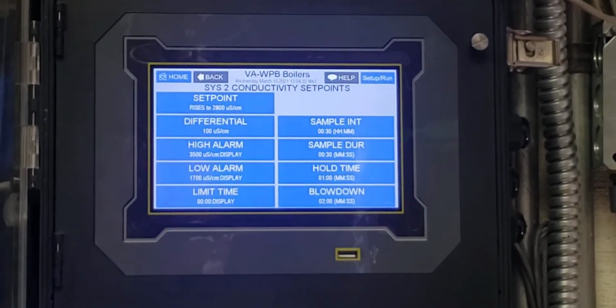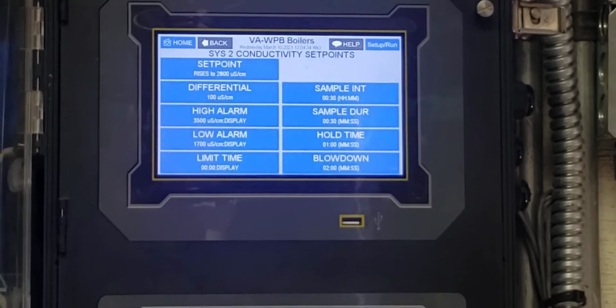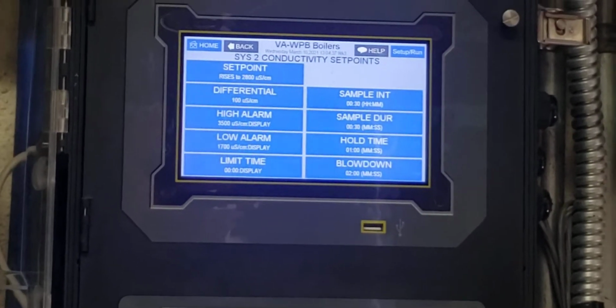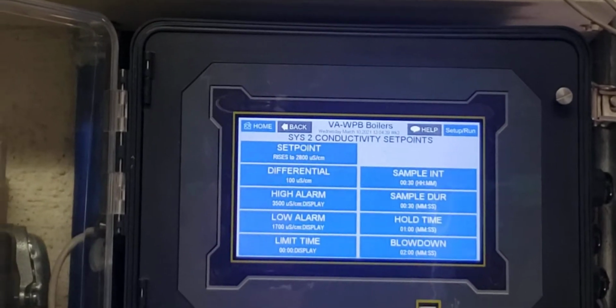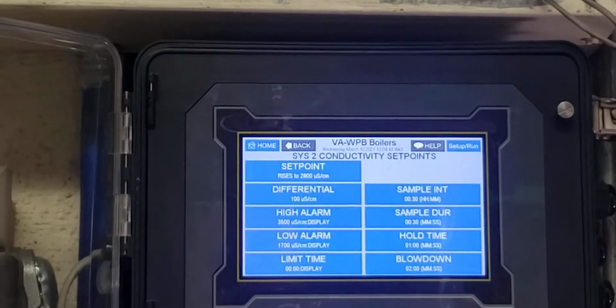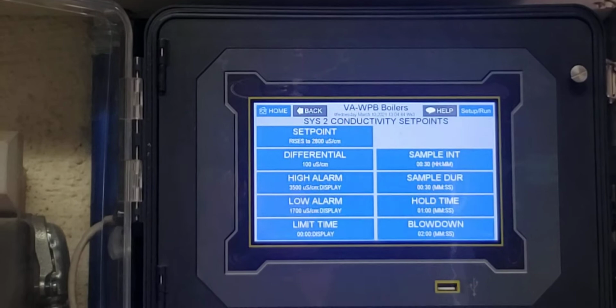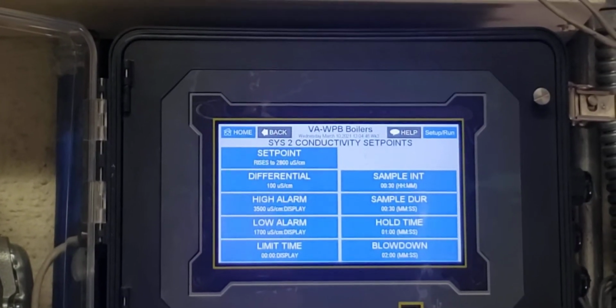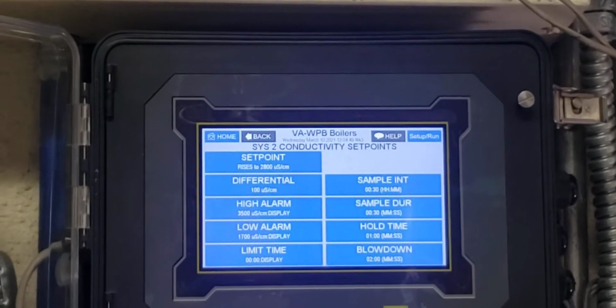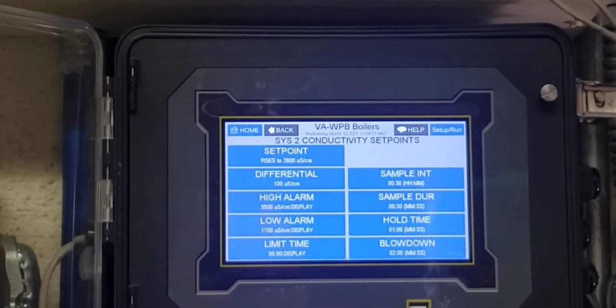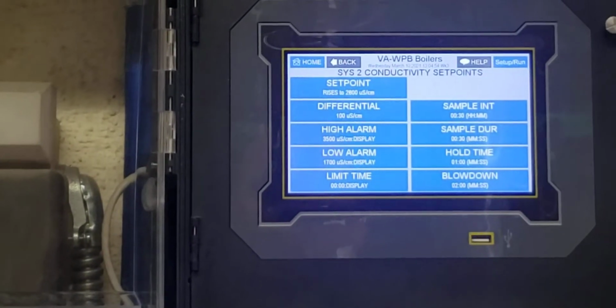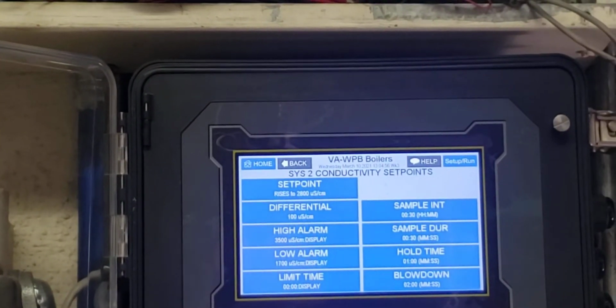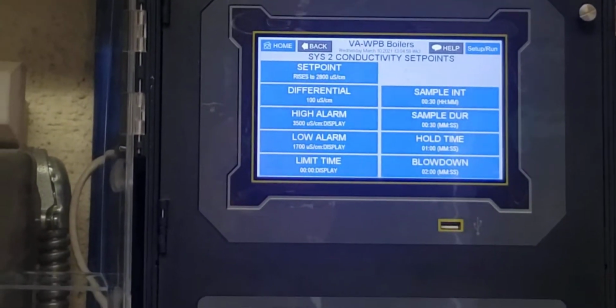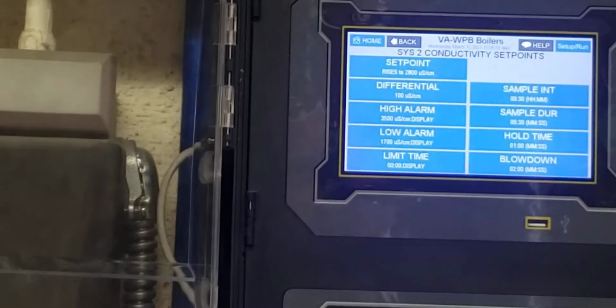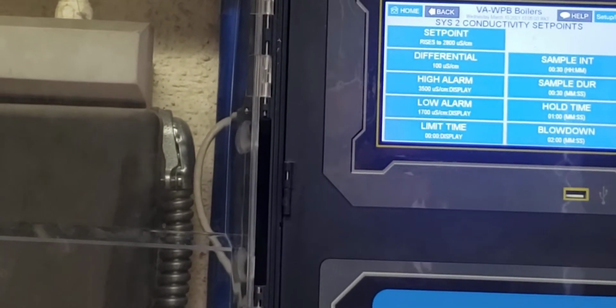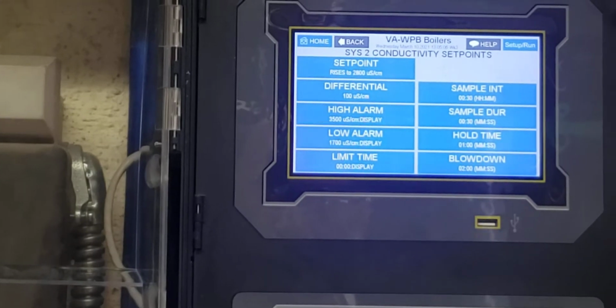It was the amount of blowdowns we were going through. When it went to blow down, I was trying to see if it needed to blow down, because I think it was originally set for like 15 minutes, and I was like, we shouldn't have to blow down for 15 minutes. And then take a sample for like 5 minutes? We shouldn't have to sit there for 5 minutes to take a sample. Yeah, it was always blowing down. So I changed that one as an experiment compared to the one you had already. Maybe the third one is probably what you set it at.